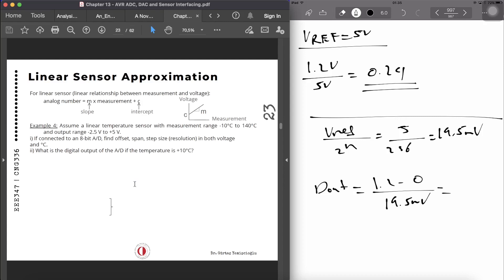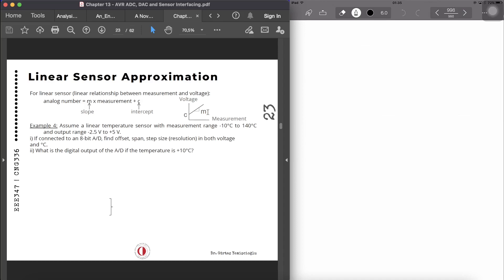Now let's look at linear sensor approximation. Linear sensors give a linear relationship between the measurement and the output voltage. For example, minus 10 degrees corresponds to minus 2.5 volts — a linear voltage-versus-measurement relationship. The slope m and intercept c can be calculated. The example is: assume a linear temperature sensor with a measurement range of minus 10 degrees to 140 degrees.